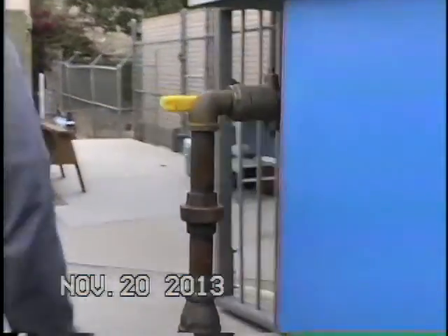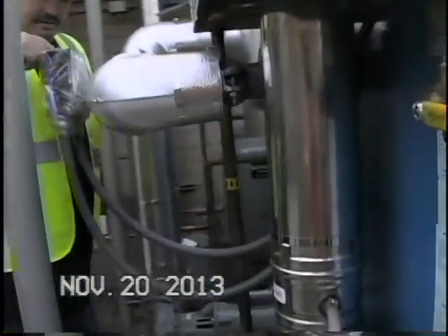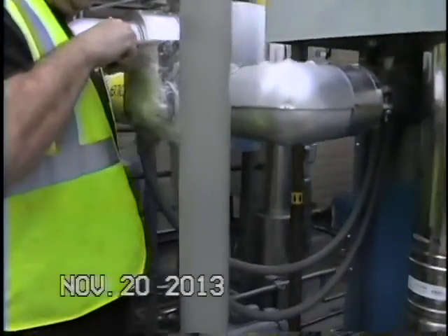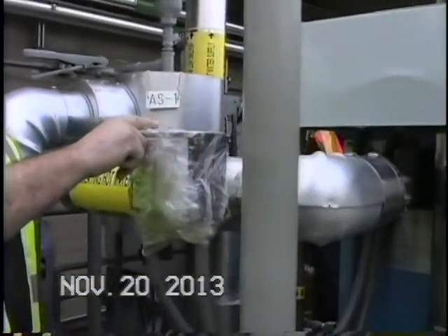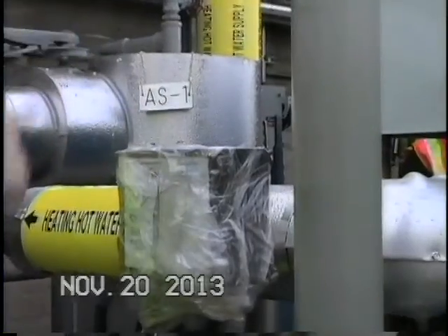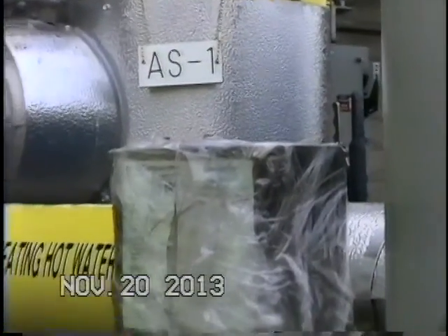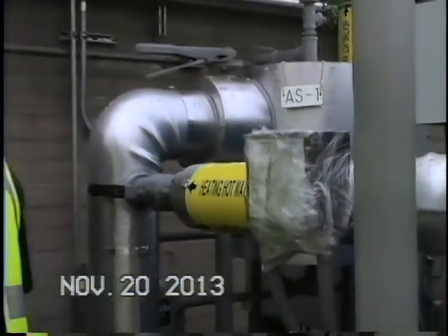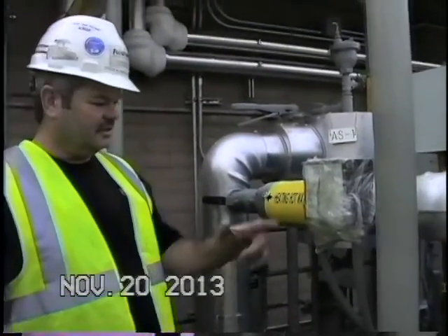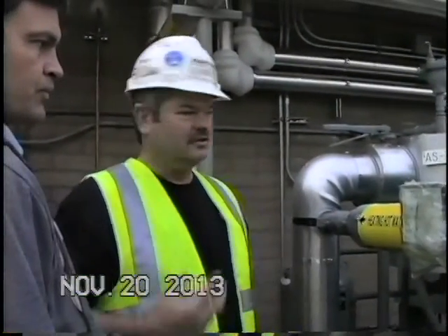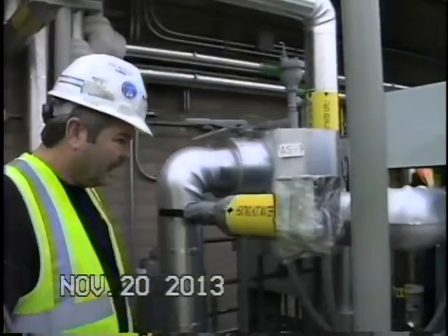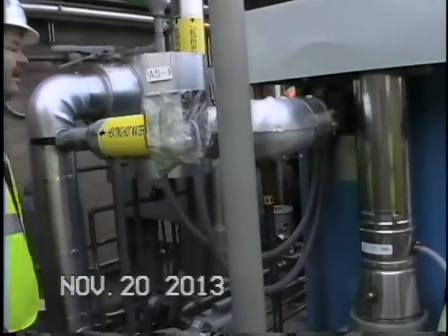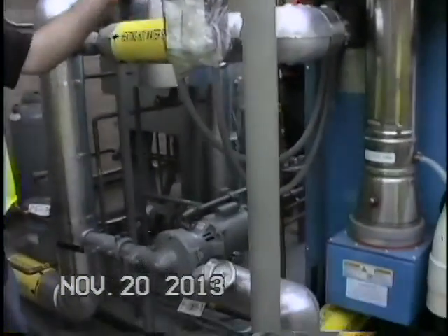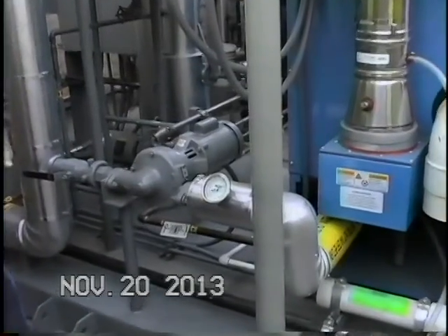Over here, there's also another test button. So here's your test button, and that's going to switch states, and it's going to do the same thing. That's on an interlock, it's going to say interlock. So this is another low water cutoff though, two spots. And this one does not have the flow switch, so these two are what's controlling it.